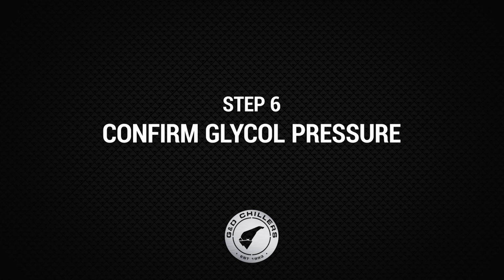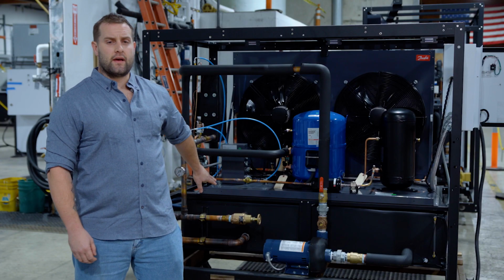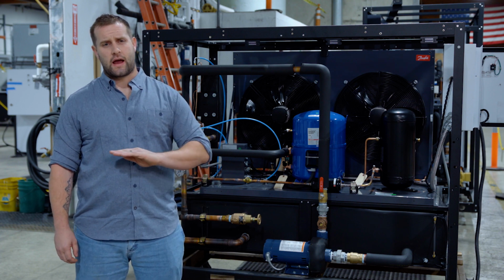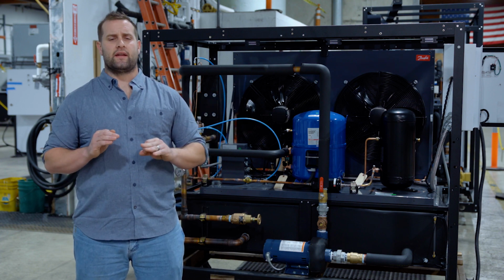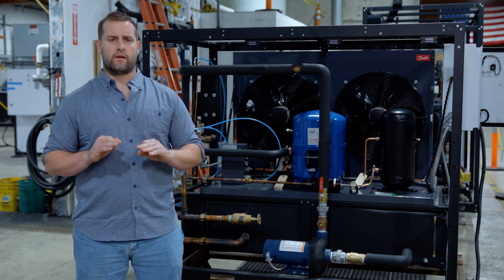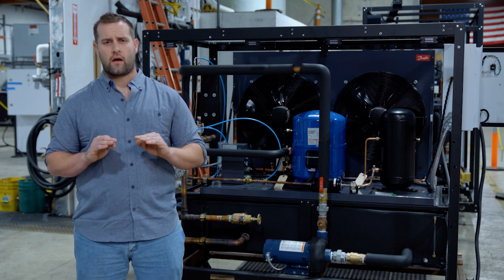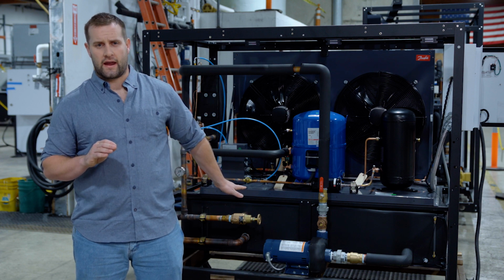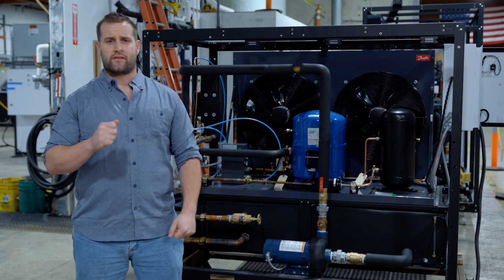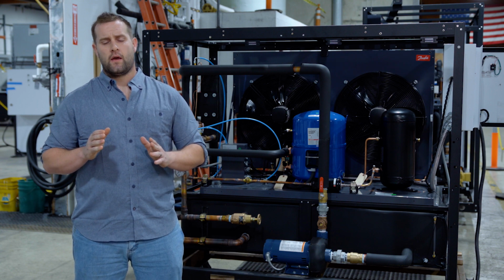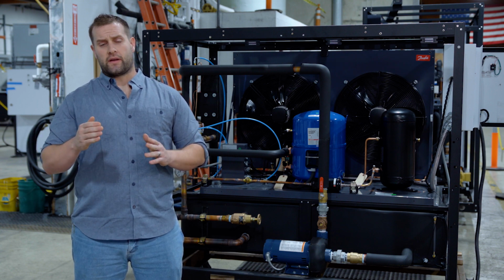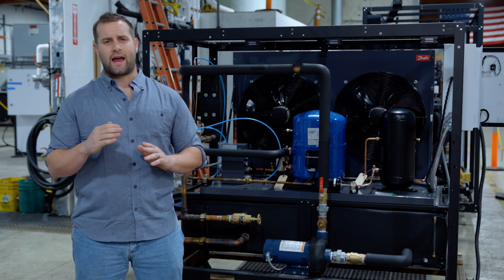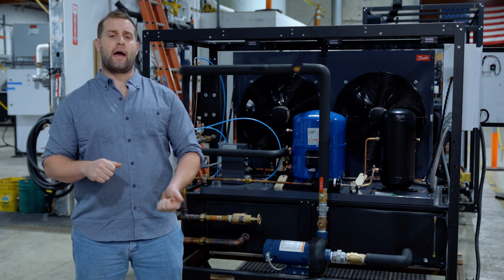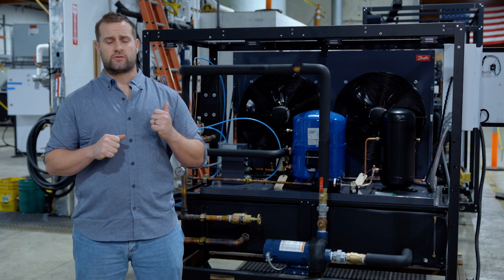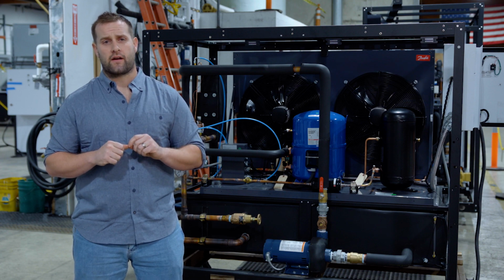All right, so the next step on the startup, you're going to take the opportunity to check your bypass pressure. There's a bypass valve in the unit that's going to regulate the pressure outgoing to your process. We set that at 20 psi for these horizontal air units. You're going to shut your supply and return ball valve temporarily and look at the analog gauge with the chiller just circulating within itself and verify that that's 20 psi. Since you do this after adding your glycol mixture, this gives you a little bit of time, because after about half an hour, you're going to want to go back and re-verify your glycol mixture with a refractometer. Again, you're looking for 35%.